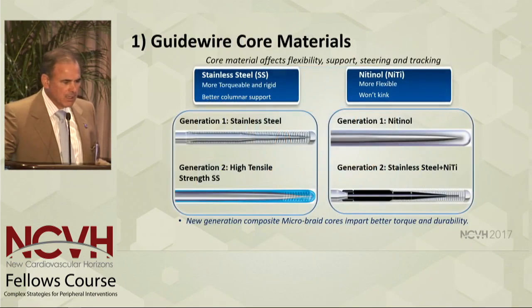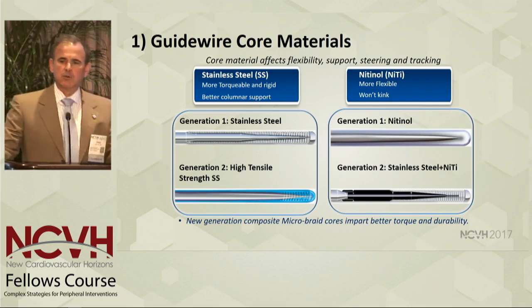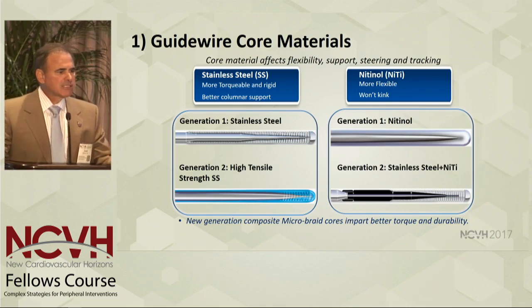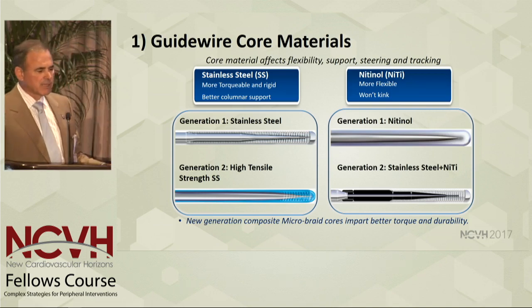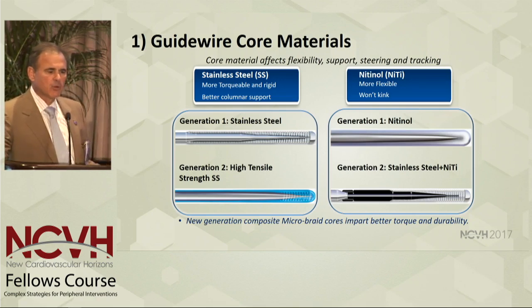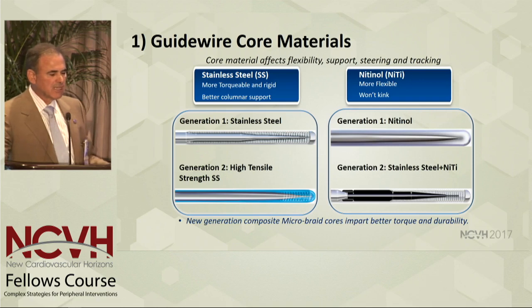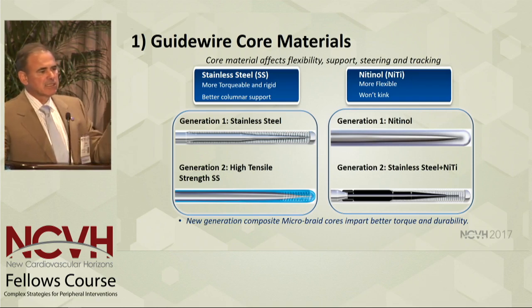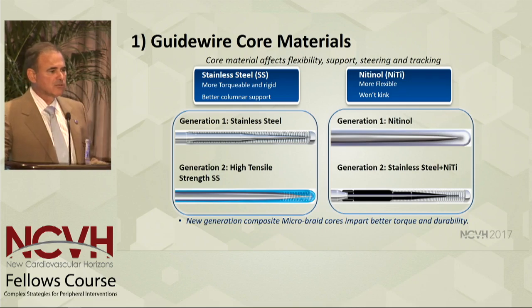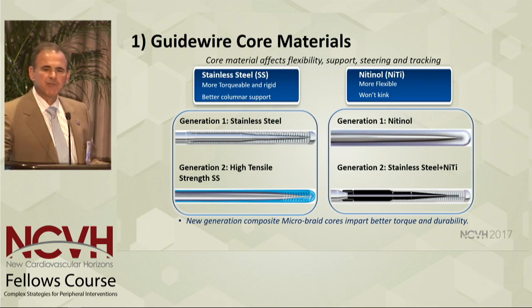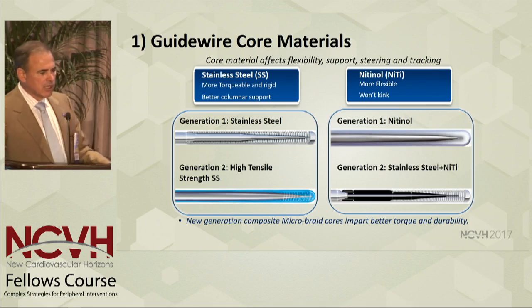The original core material of wires was surgical stainless steel. Now this has been replaced by and large in most wires with high tensile stainless steel, which is not only stronger, but it torques better and it tends to kink less. We also have, as a core material, nitinol. Wires like the glide wire have a nitinol core — it doesn't tend to kink. And we have hybrid wires made of stainless steel coupled with nitinol. Nitinol is more flexible and it won't kink, but we have better columnar support and torque with surgical stainless steel.